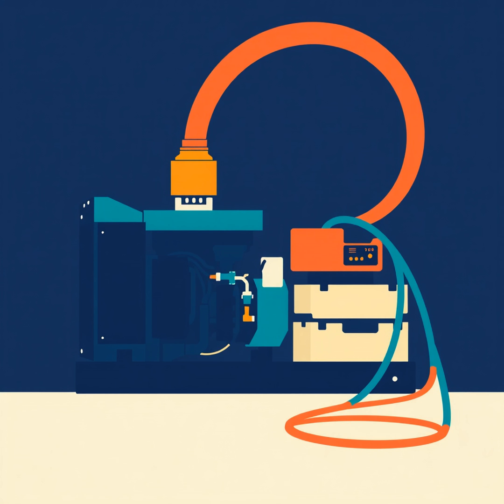In a truly redundant system, you have two completely separate paths for the power to travel. We call this an A and B power feed. You have two different utility feeds coming from two different substations, two different sets of switchgear, and two different sets of wiring all the way to the equipment. If you look at high-end servers or medical imaging machines, they actually have two power plugs. One goes to the A side and one goes to the B side. If any single component along either path fails, a breaker trips, a wire melts, a transformer blows, the equipment keeps humming along on the other one.